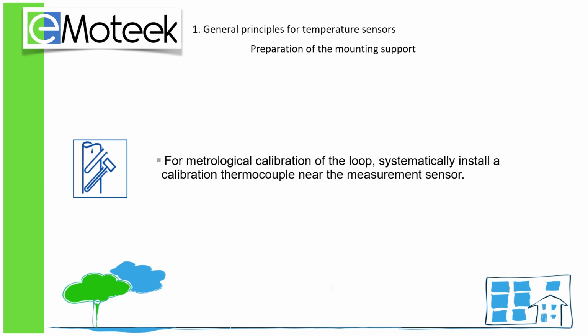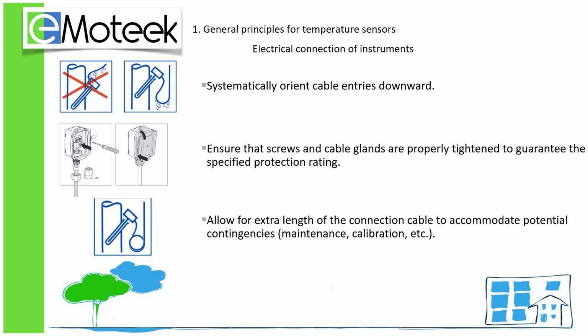We can now move on to the electrical connection of the instruments. Very well. Always orient the cable entries downward. Ensure proper tightening of the screws and cable glands. To ensure the protection rating, right? Exactly. Also, keep some extra cable length for any unforeseen events, such as maintenance or calibration.